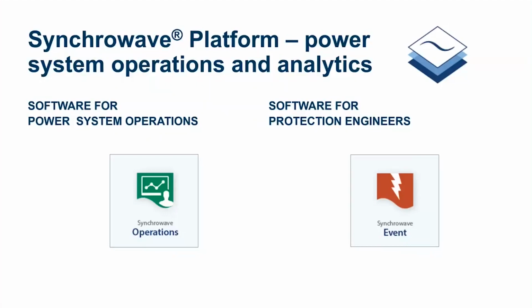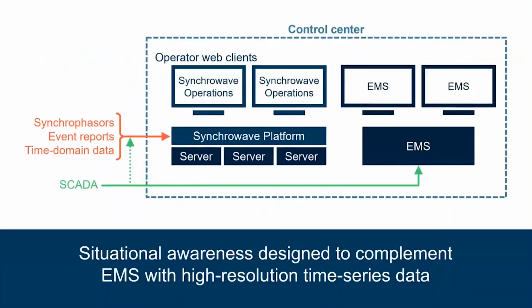The software actually provides situational awareness by integrating GIS location information with high resolution time series data from protection relays or synchrophasors. So again, this software is supposed to complement traditional SCADA and EMS systems. It's not supposed to replace them because it can provide high resolution data which was previously not possible with SCADA and EMS systems. The servers mentioned on the slide bring all the data to the software.